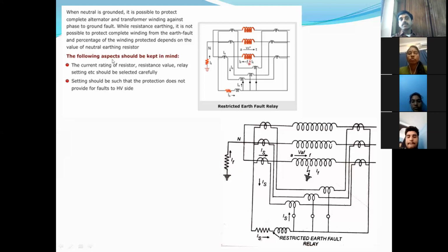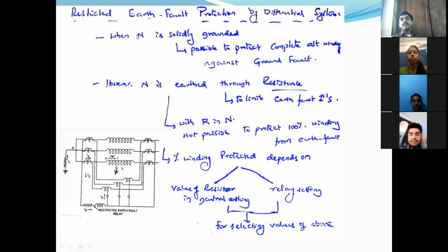The following aspects should be kept in mind: the current rating of the resistor, resistance value, relay setting, etc. should be selected carefully. Setting should be such that the protection does not operate for faults on the HV side. Let us see this, the discussion we continued. Restricted earth fault means that for earth faults, there is a restriction of the winding protected.